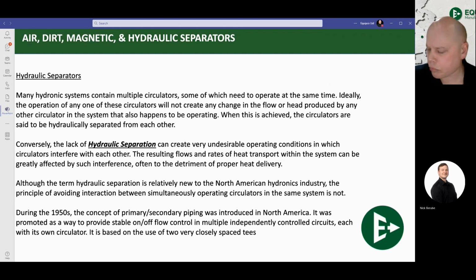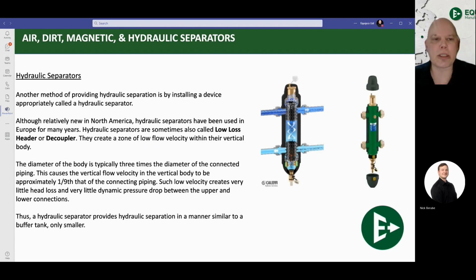The last piece inside of this portion here is our hydraulic separation. Hydraulic separation, like I mentioned, separates the flow from the boiler from our system. The boiler gets its own flow, the system gets its own flow. They completely decouple the flow from the two. The boiler needs to see flow continuously to whisk away heat from a heat exchanger. The system can fluctuate wildly in the flow that it requires, especially in zoned systems.